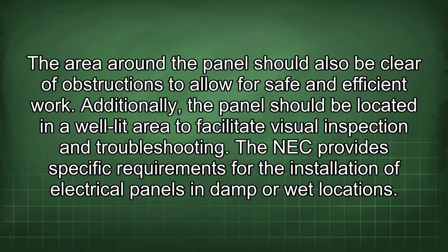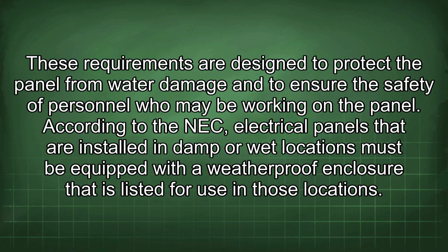The NEC provides specific requirements for the installation of electrical panels in damp or wet locations. These requirements are designed to protect the panel from water damage and to ensure the safety of personnel who may be working on the panel. According to the NEC, electrical panels that are installed in damp or wet locations must be equipped with a weatherproof enclosure that is listed for use in those locations.